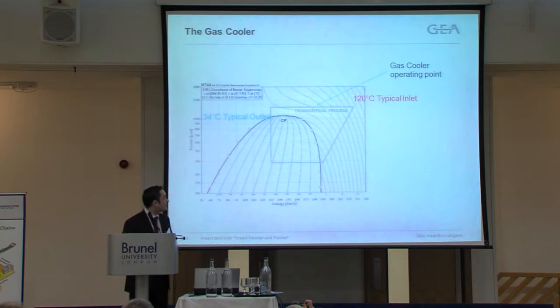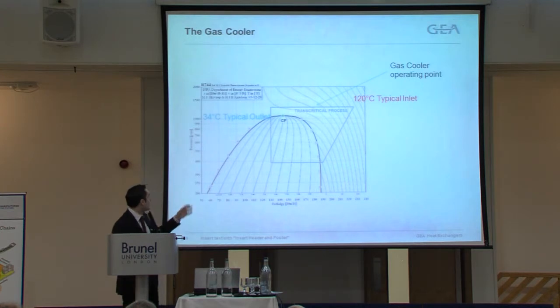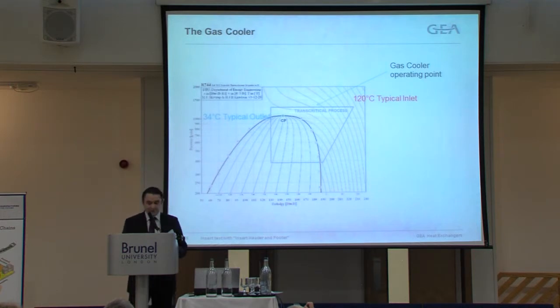Okay, so in summary, a more detailed pressure enthalpy here. Typical operating condition, you'd be entering the gas cooler at around about 120 degrees C, trying to leave the gas cooler at approximately 34 degrees C if you had a 32 degrees C air on. So that means we've got an approach temperature, as we call it, of 2K, which is very tight, you would say, which is why often you need a different style of heat exchanger, a lot more surface to achieve those very tight temperature differences.